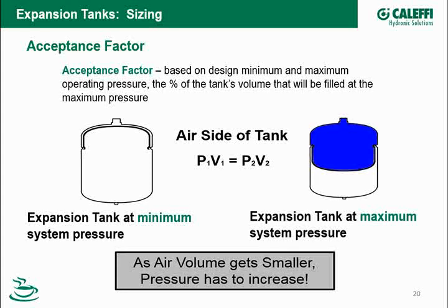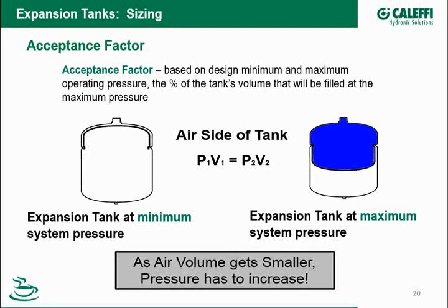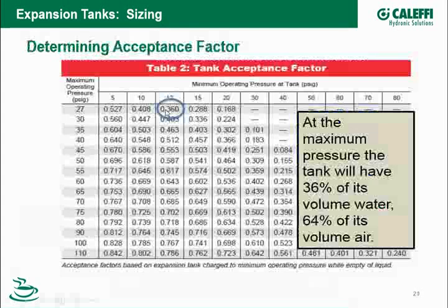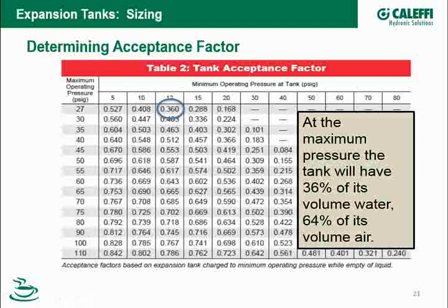So if I go to some charts, acceptance factor charts, for instance, if I say minimum pressure is going to be 12 psi and the maximum is going to be 27, I look on here and I come up with an acceptance factor of 0.36. So at 12 psi, the tank is full of air. At 27 psi, 36% of that tank is holding water, and 64% of it is holding air. Okay? And this is not a factor of tank size. This is a consistent factor based on the pressure swing of the tank itself.